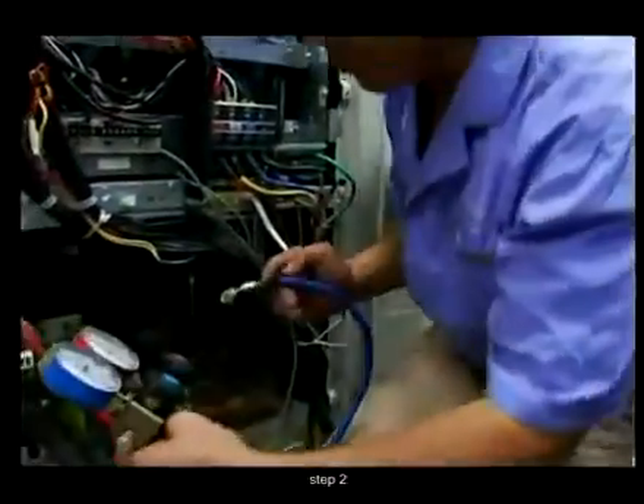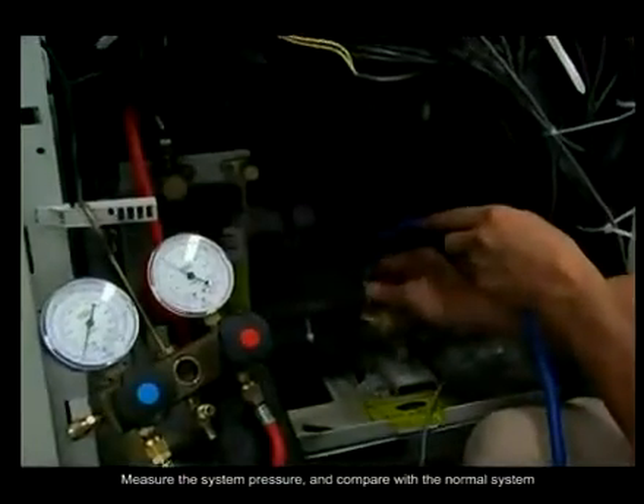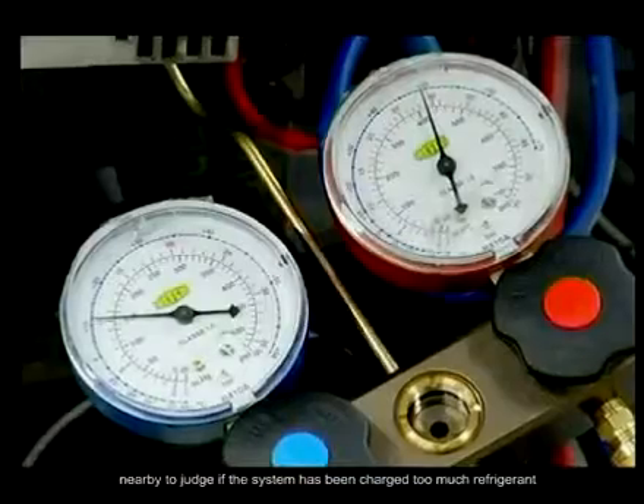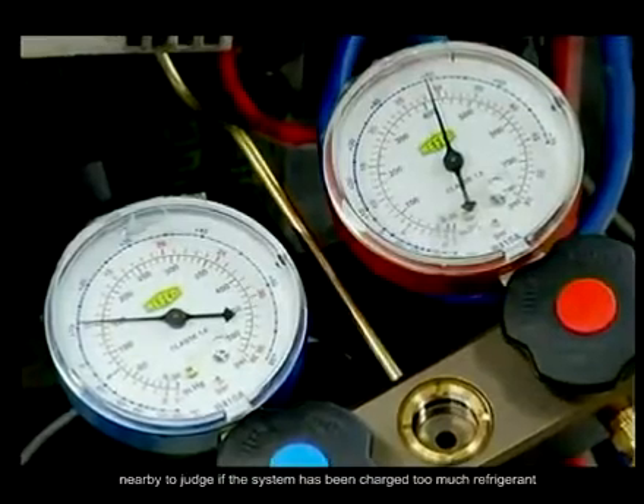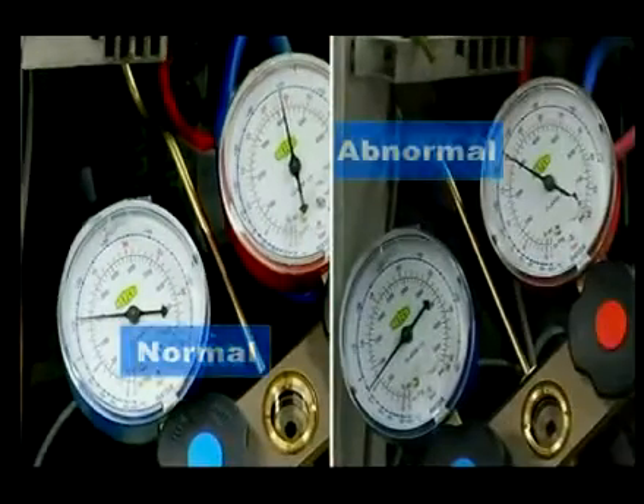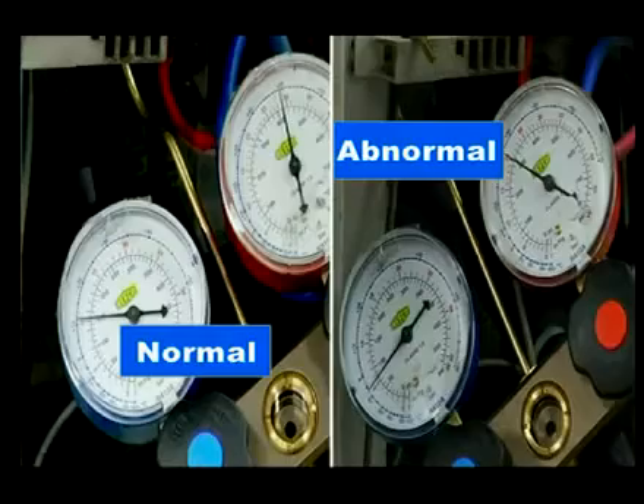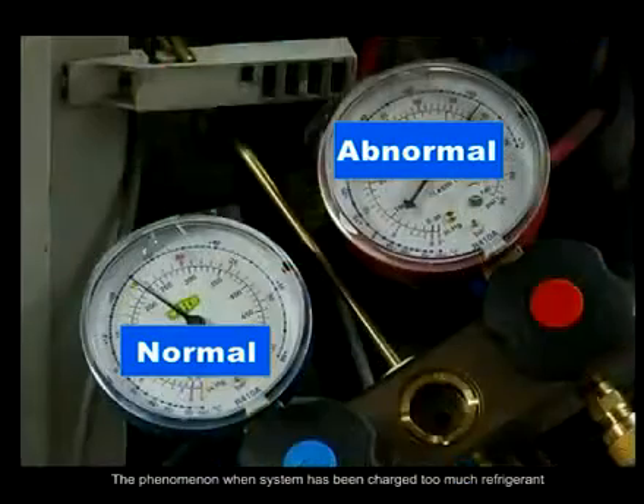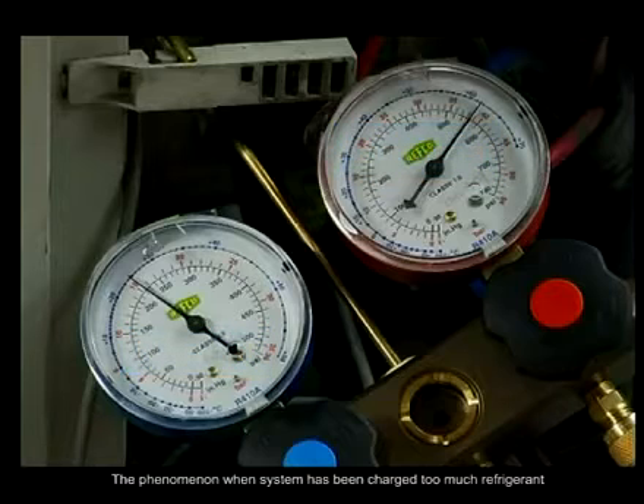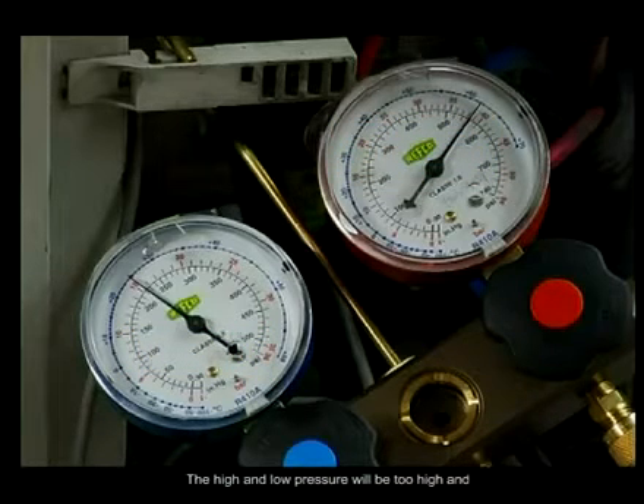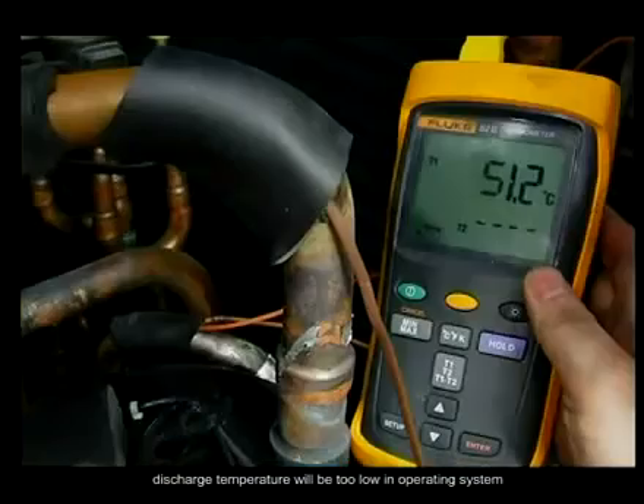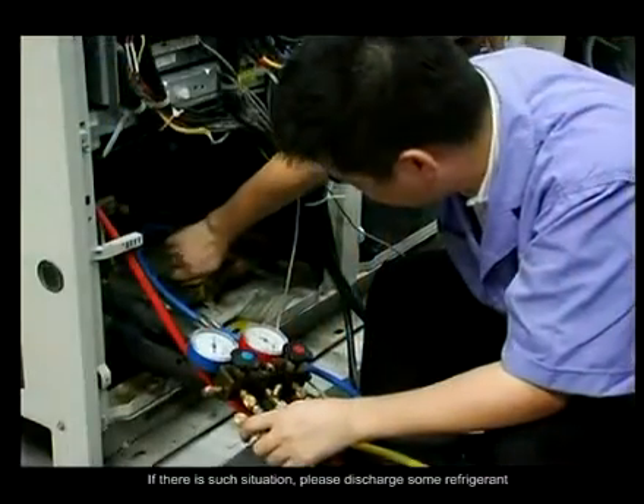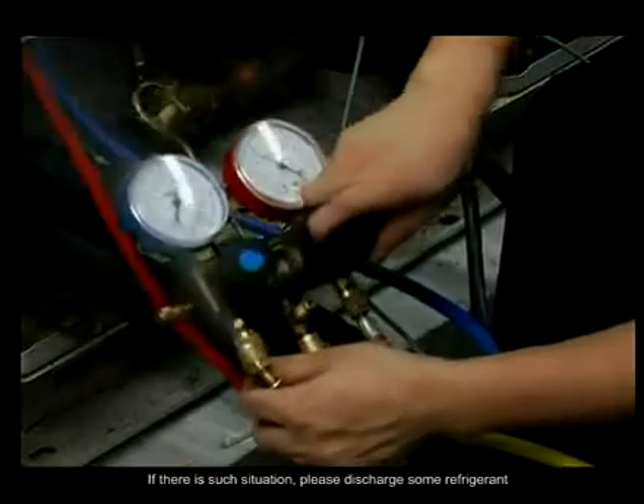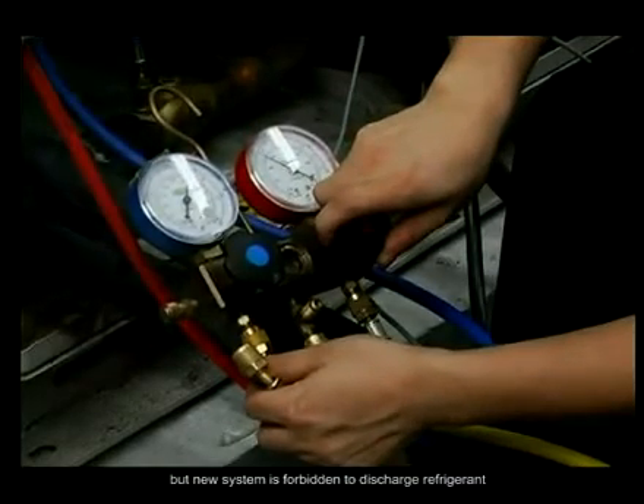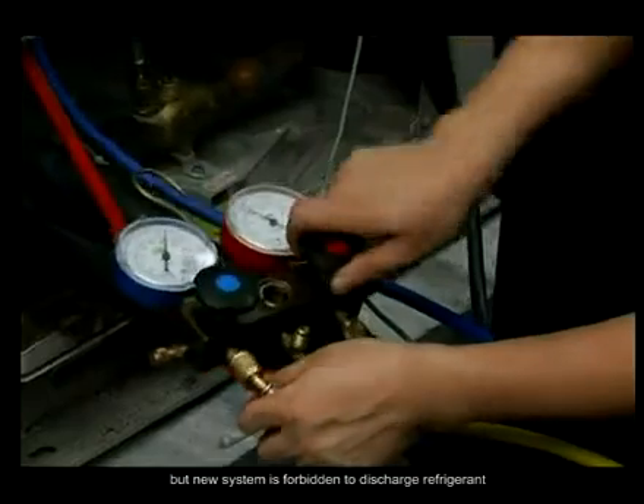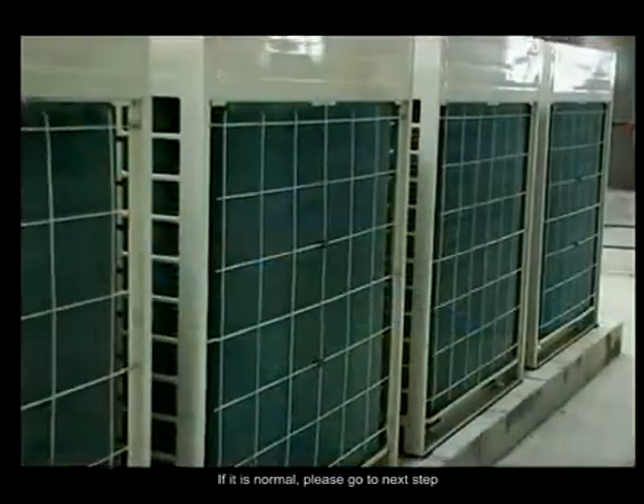Step 2. Measure the system pressure and compare with the normal system nearby to judge if the system has been charged with too much refrigerant. The phenomenon when the system has been overcharged: the high and low pressure will be too high and the discharge temperature will be too low in the operating system. If there is such a situation, please discharge some refrigerant, but a new system is forbidden to discharge refrigerant. If it is normal, please go to the next step.